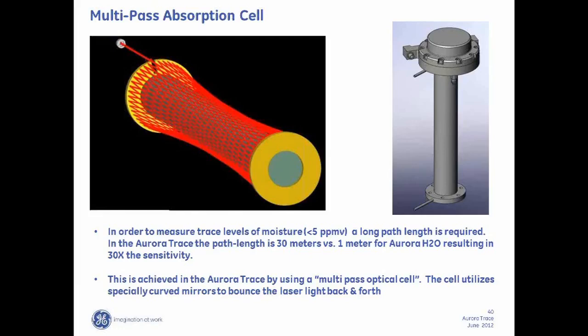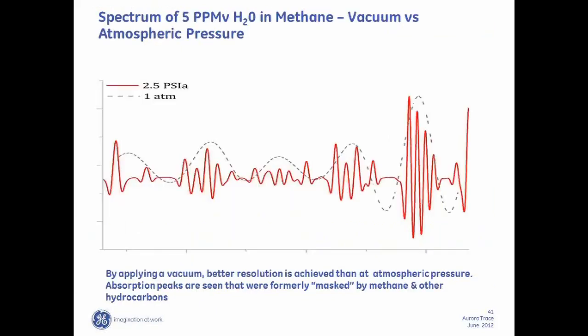So the effect of the pressure broadening is shown on this slide, and the dotted line is at atmospheric pressure. The same gas under 2.5 psia is the red line, and you can see that there's a lot more detail on the red line than what you had on the dotted black line. And that detail comes out as sort of like looking at a high-definition television versus a conventional television. You're seeing much more detail. There's actually about 5 discernible peaks that come out under the vacuum condition, and there's one sort of broadened peak that comes out under the atmospheric condition that's attributable to water.